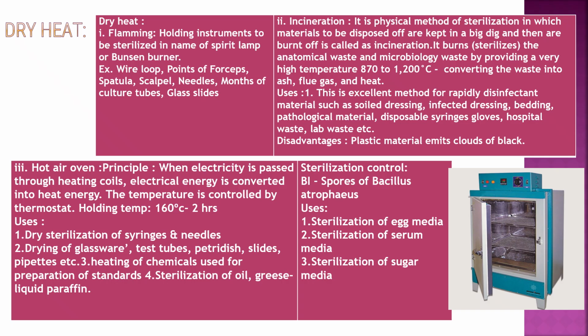Sterilization control of the hot air oven: biological indicator, the spores of Bacillus atrophaeus. Other uses of the hot air oven: sterilization of egg media, serum media, sugar media.